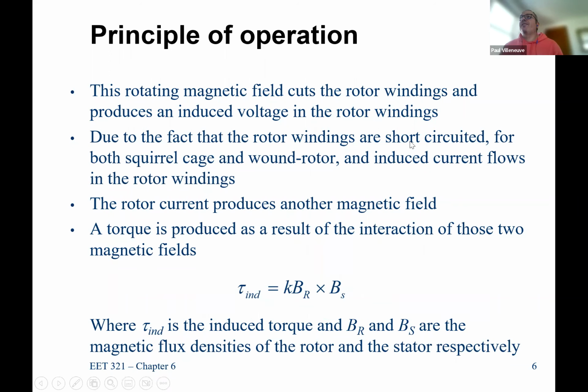And that's why these have to be short-circuited, whether it's wound rotor or squirrel cage. If it's wound rotor, it's not necessarily short-circuited, but it's sent back to something external, which allows current to flow. Okay. So in a wound rotor, it's not 100% induced, it's provided externally. In a squirrel cage, everything is induced. So that's the major difference that we have here. That rotating magnetic field cuts the rotor windings. The changing magnetic field induces a current in the rotating winding. And that's induced in a 3-phase set of windings on the rotor.